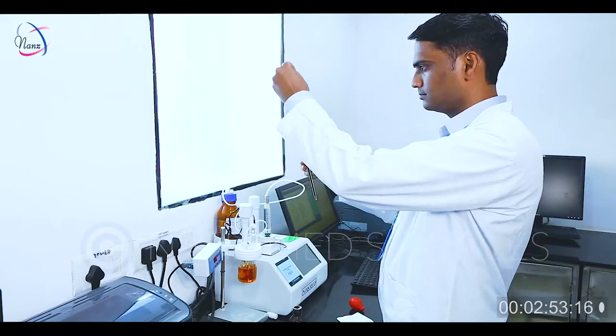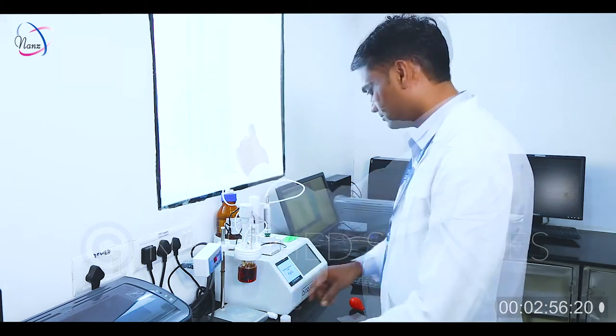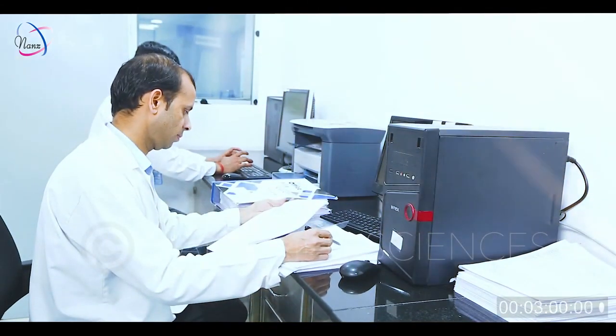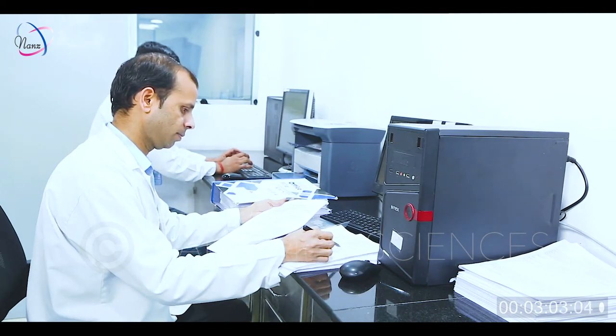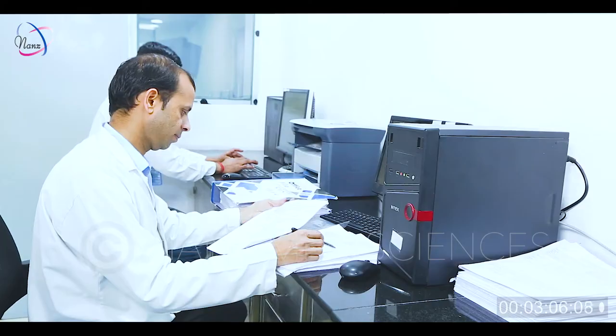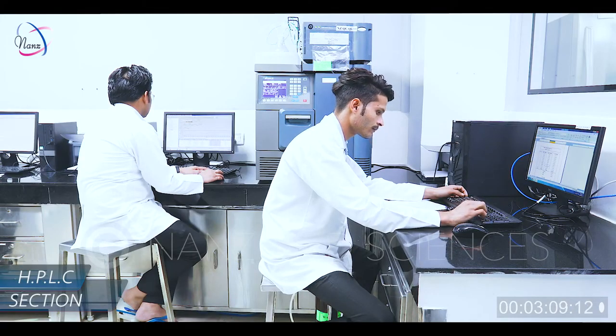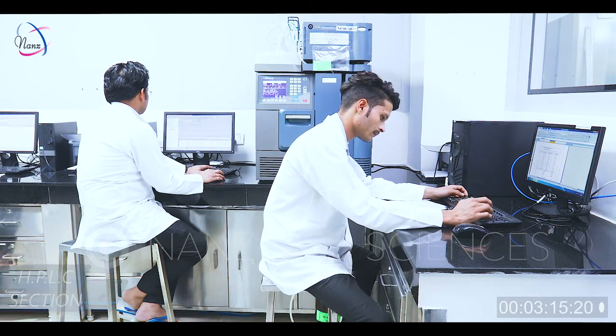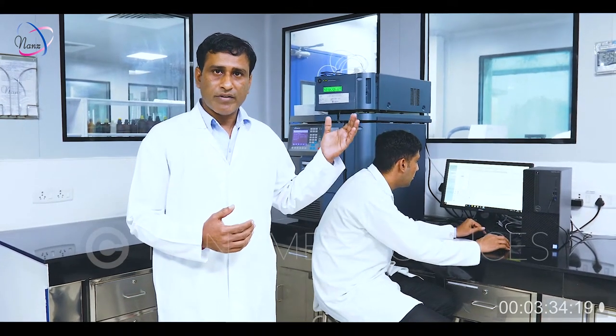The trained and qualified QC analyst performs the analysis as per the work allotment. All the analytical records are thoroughly reviewed through a two-level review process before taking any decision on material release. The analyst is first trained and then undergoes the analyst qualification procedure before being allowed to do any kind of analysis on the HPLC. The QC lab is equipped with 4 Waters HPLC systems. All the systems are fully compliant with 21 CFR Part 11. Validation is performed for user management, access controls, password policies, data management, and audit trail activation, etc.